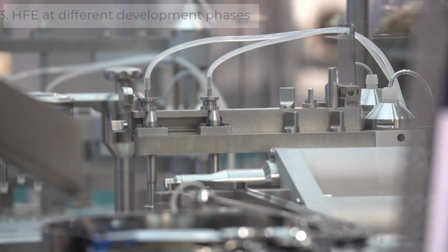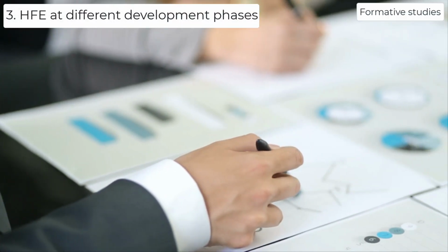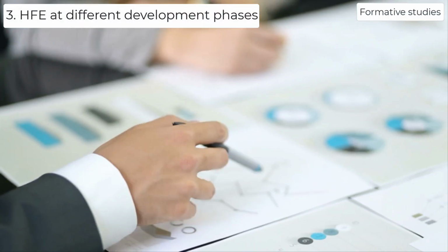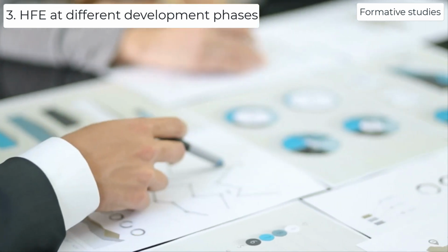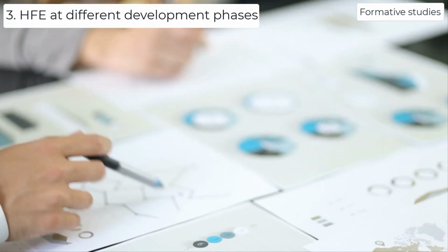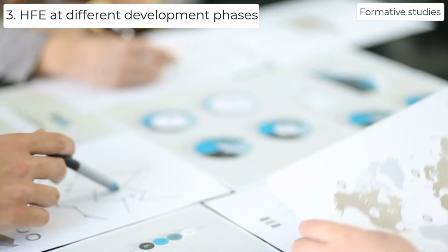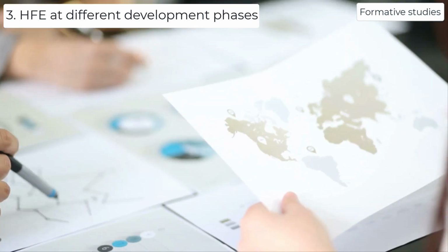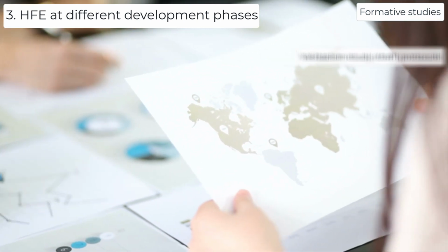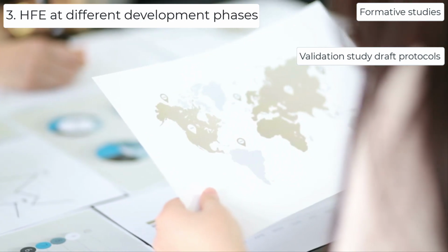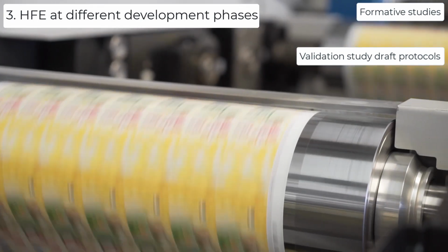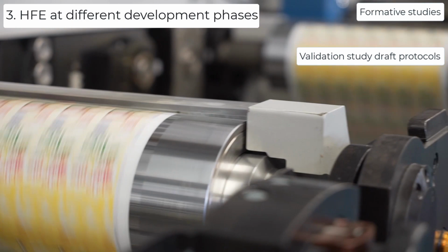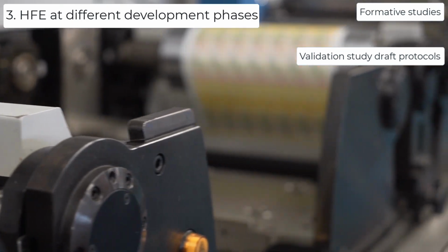Topic 3. Human factors considerations at different development phases. The FDA reviews formative human factors evaluations as part of a draft protocol submission, the human factors report in the marketing application, or both, to better understand the development of the user interface design of the combination product. The FDA will review draft human factors validation study protocols within the lead center's established timeframe. If the draft labeling is included, the labeling leads in each center will conduct a pre-study review to prevent post-study revisions.